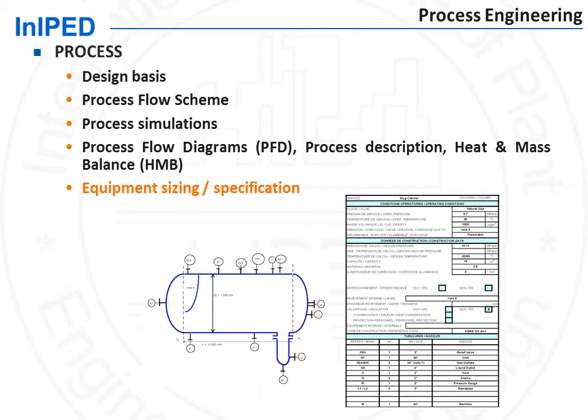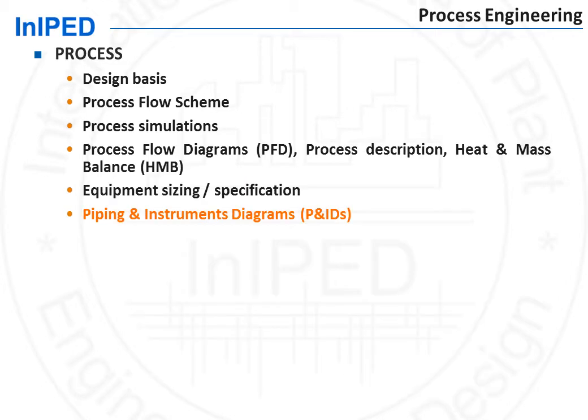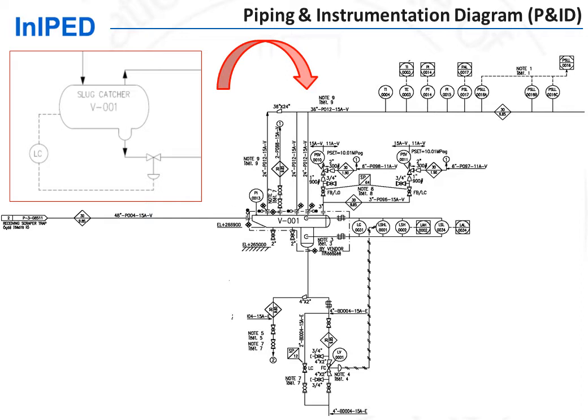The process engineer then needs to go into more details of the plant operating environment. This is done by preparation of piping and instrumentation diagrams. The process flow diagrams that we have seen earlier only show the main process lines, the process equipment, as well as the control valves. Much more detail needs to be defined by process. These details are shown on the piping and instrumentation diagrams.